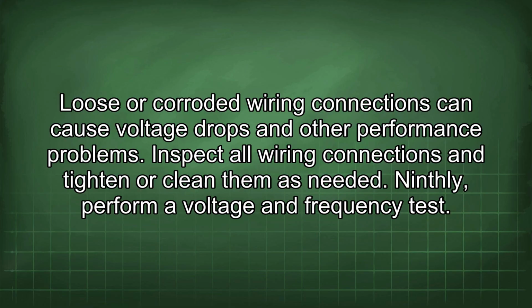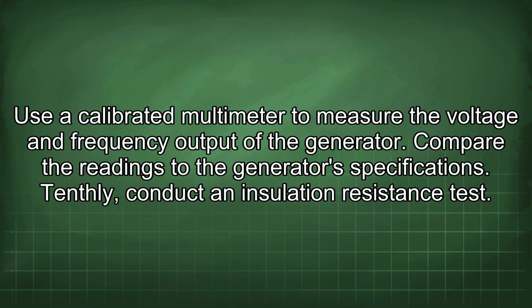Ninthly, perform a voltage and frequency test. Use a calibrated multimeter to measure the voltage and frequency output of the generator. Compare the readings to the generator specifications.